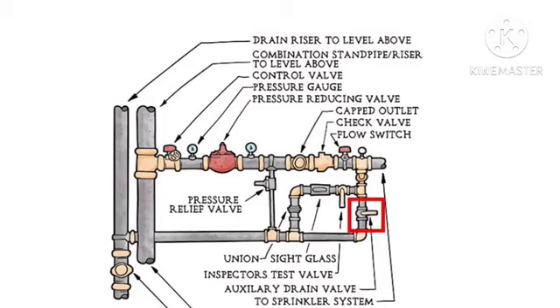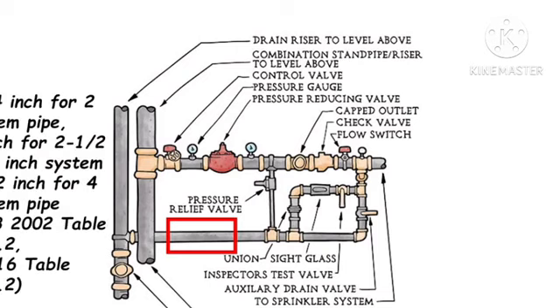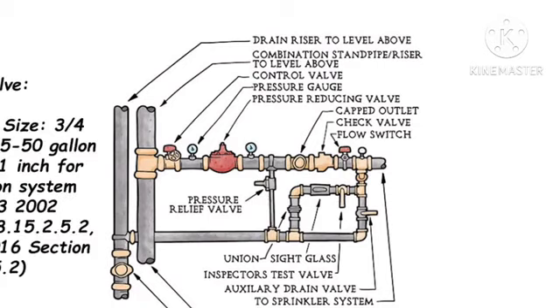Auxiliary drain valve. Permits faster draining of the system, as opposed to only draining the inspector's test valve. Check valve. Can help reduce false water flow alarms on floors where sprinklers have not activated. Drain pipe. Size: 3/4 inch for 2-inch system pipe, 1¼ inch for 2.5 to 3.5-inch system pipe, or 2 inch for 4-inch system pipe. Drain valve. Minimum size: 3/4 inch for 5 to 50 gallon system, 1 inch for above 50 gallon system.